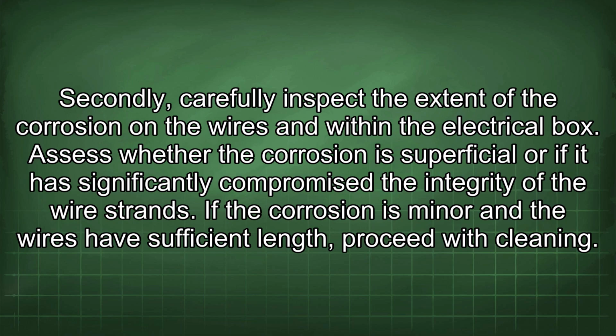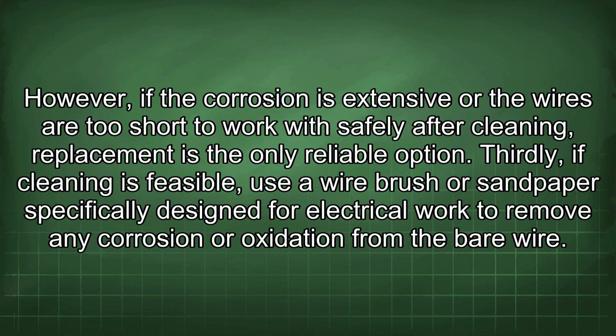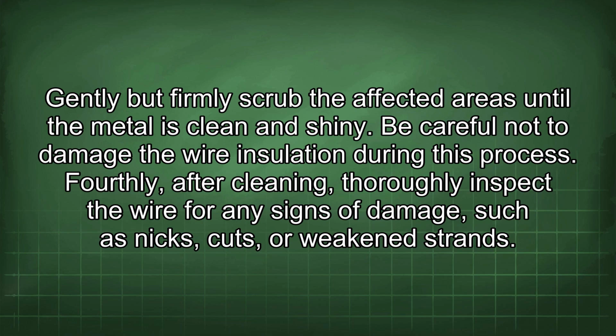If the corrosion is minor and the wires have sufficient length, proceed with cleaning. However, if the corrosion is extensive or the wires are too short to work with safely after cleaning, replacement is the only reliable option. Thirdly, if cleaning is feasible, use a wire brush or sandpaper specifically designed for electrical work to remove any corrosion or oxidation from the bare wire. Gently but firmly scrub the affected areas until the metal is clean and shiny. Be careful not to damage the wire insulation during this process.